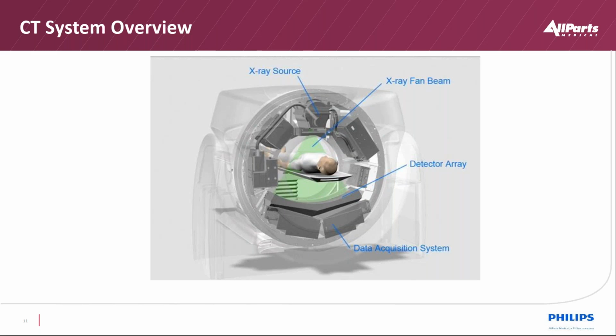And again, as I said, in CT we require a minimum of 180 degrees rotation to produce an image. But originally we did 360. The more data, the less noise in the image, is the best way to put that. And so that's one of the reasons why you'd want to do it. So the X-ray beam obviously is ionizing radiation, so we like to minimize as much as possible, but it's constrained into a slice of a thickness, maybe a millimeter, 5 millimeters, 10 millimeters of what we're interested in acquiring the data for. So we have the detector array, which is typically a crystal-based detector now. And radiation and crystals are not really friends, so to speak.